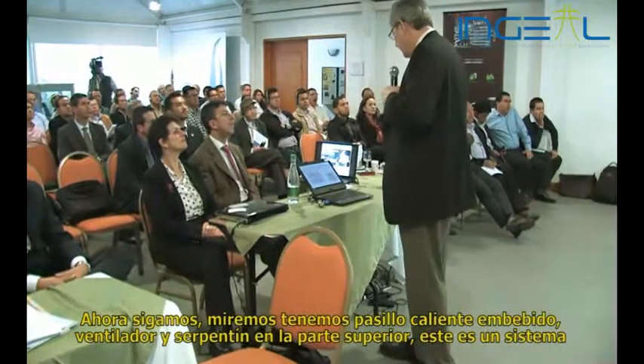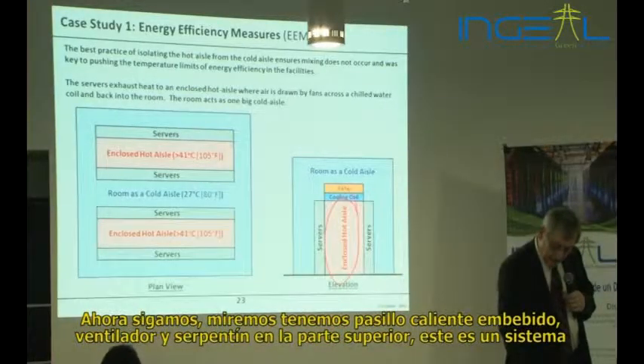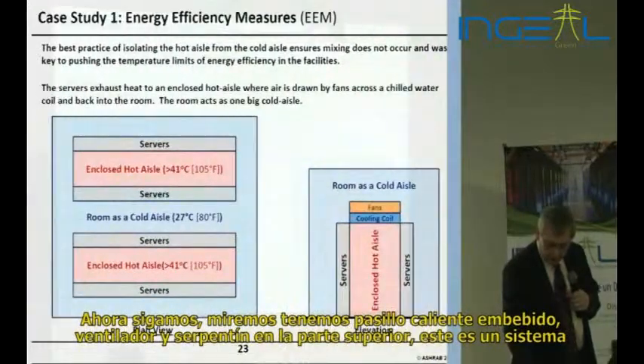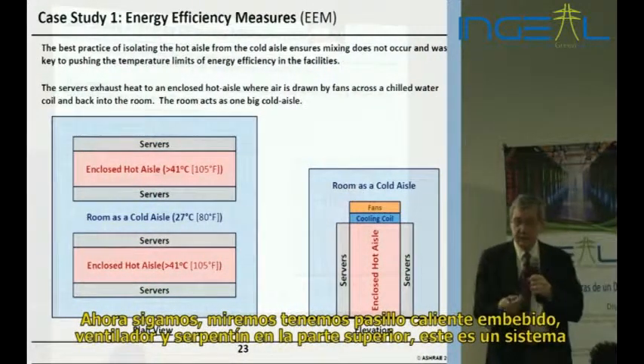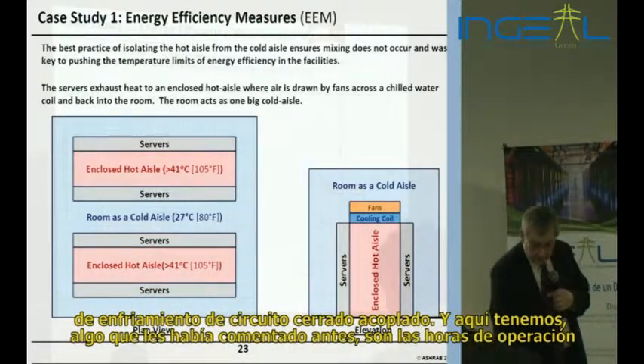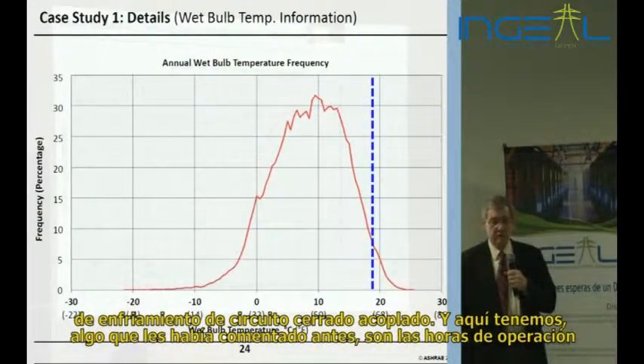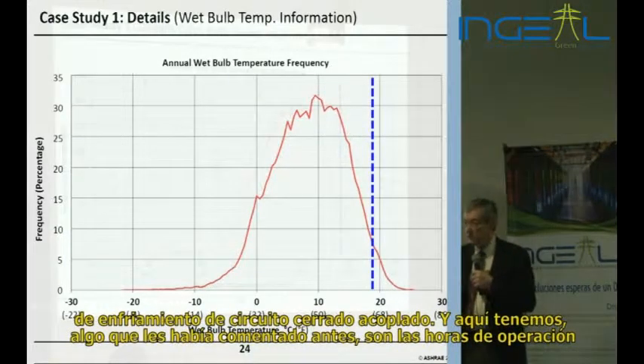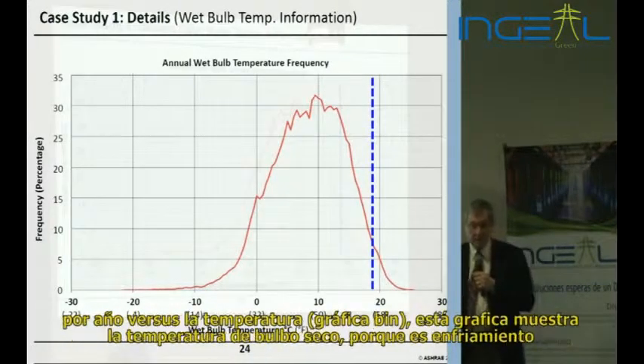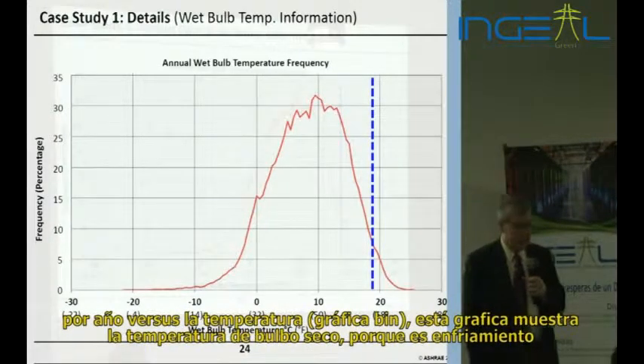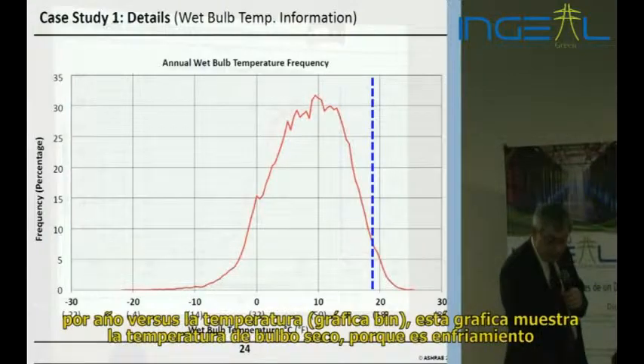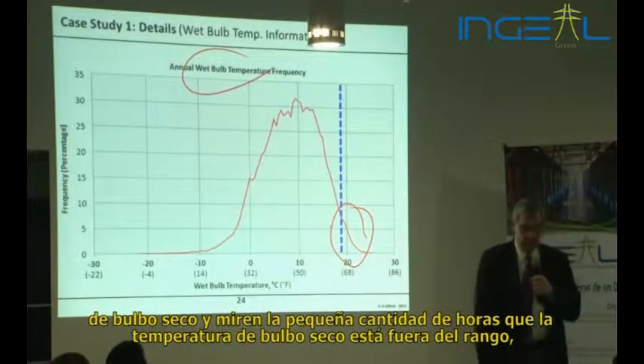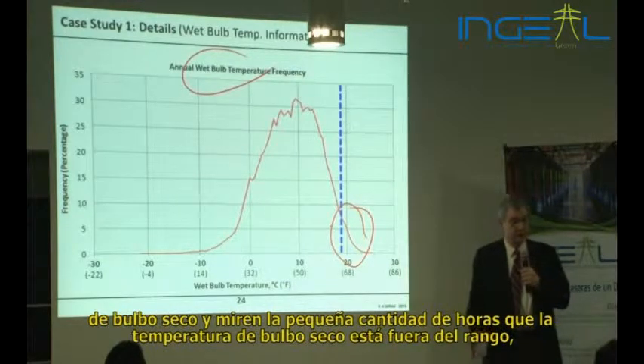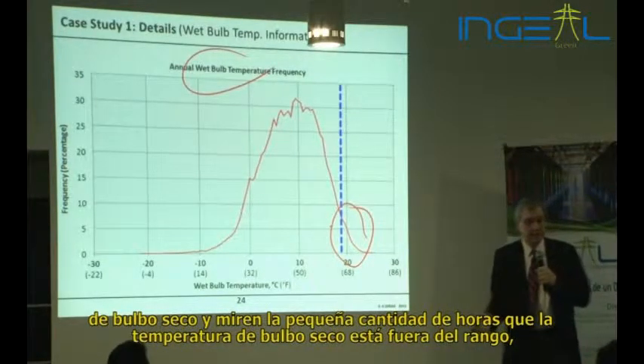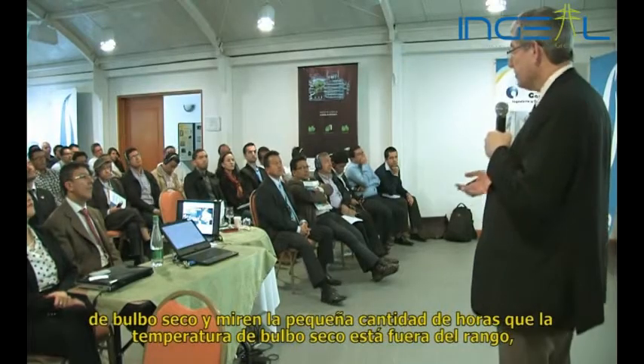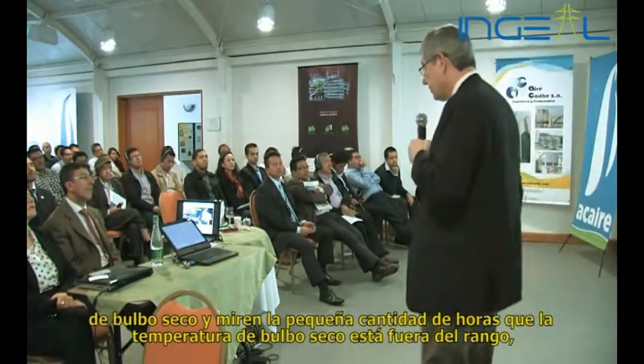So now we look - this just has an embedded hot aisle and a fan coil on top, so that's a closed circuit type of cooling system. And here shows what I was talking about earlier: bin hours. This happens to be a plot at the wet bulb level because it was wet bulb cooling. Look at the small amount of hours where the wet bulb does not conform - that's the amount of cooling you really need to do. You can size your plant based on that small amount of bin hours.